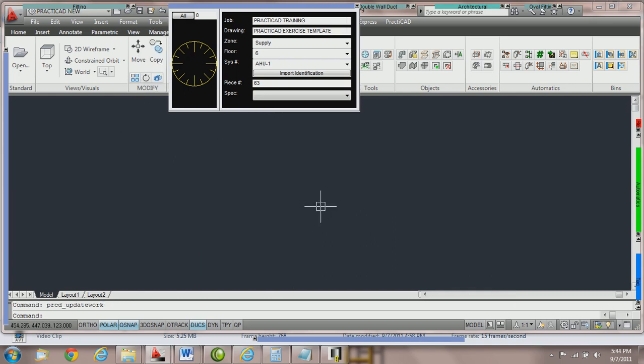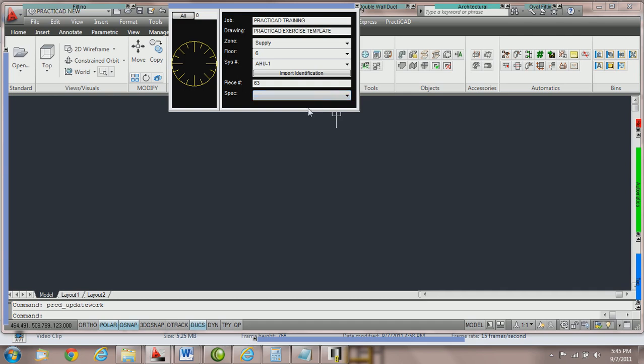Part 4 is the explanation of applying specs from the workbox. This is probably the most important part of the workbox because you should never be drawing duct without a specification in play. It's easy to add zones, floors, and system number information later. However, specification information, if you go to change, might affect the way your duct line edits. So it is proper procedure to always select the specification first and then grab your duct.